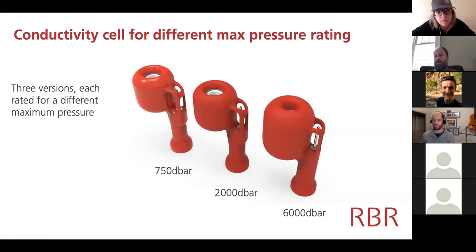In fact, most soaps will cause electrode-based cells to give erroneous readings. Even TBT, which is the carcinogenic antifoulant method that's often used in electrode cells, will contaminate the cell itself. And that's very tricky to determine because that coating happens while the cell is not in the water, and it's a function of temperature that lowers the viscosity of the TBT and helps it migrate through the cell. So depending on what you're doing, you do want to be careful. I'd also watch out for the liability on giving carcinogens to grad students.